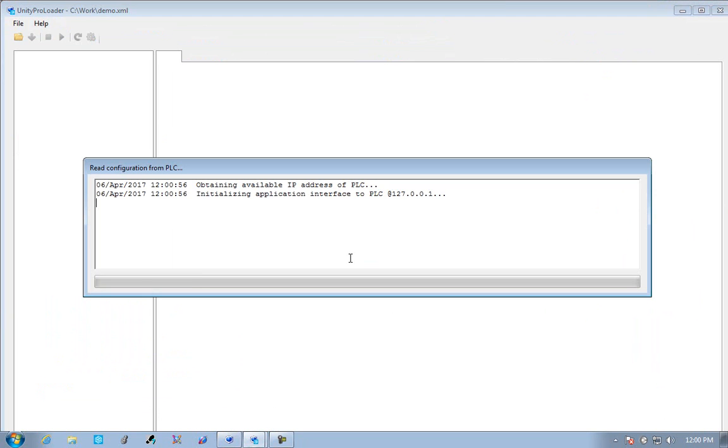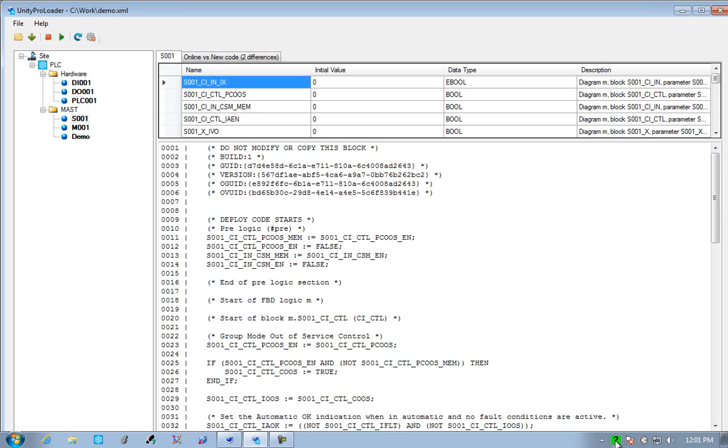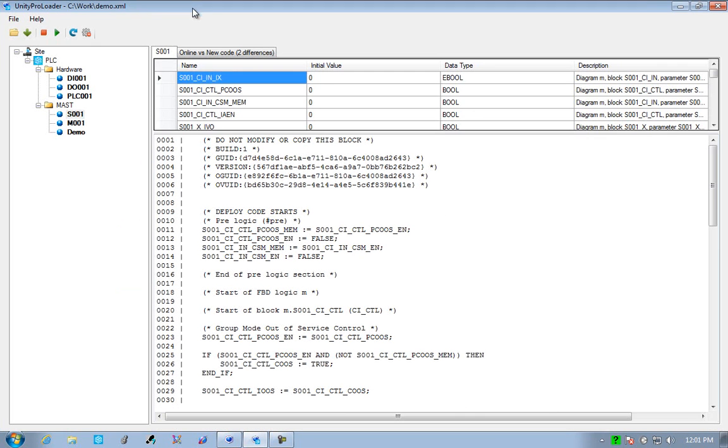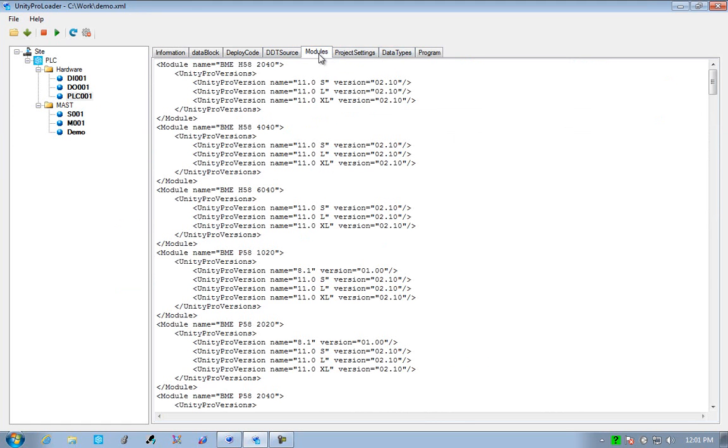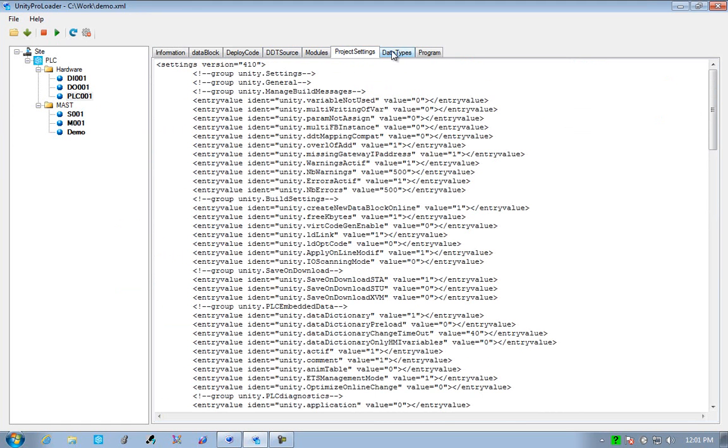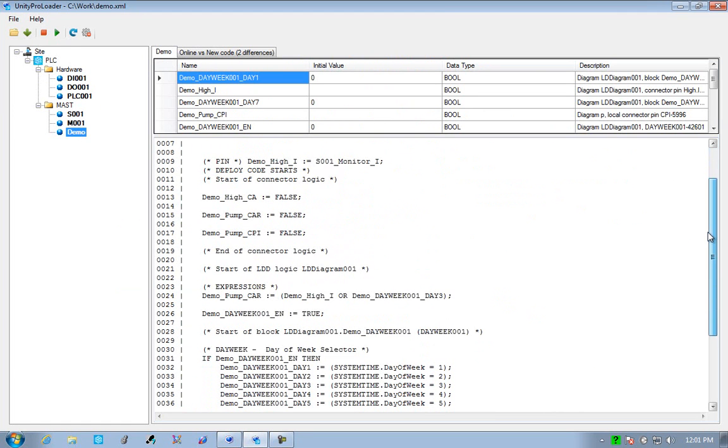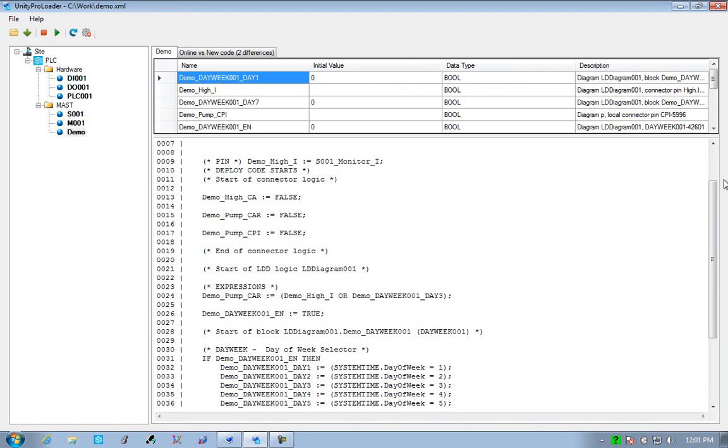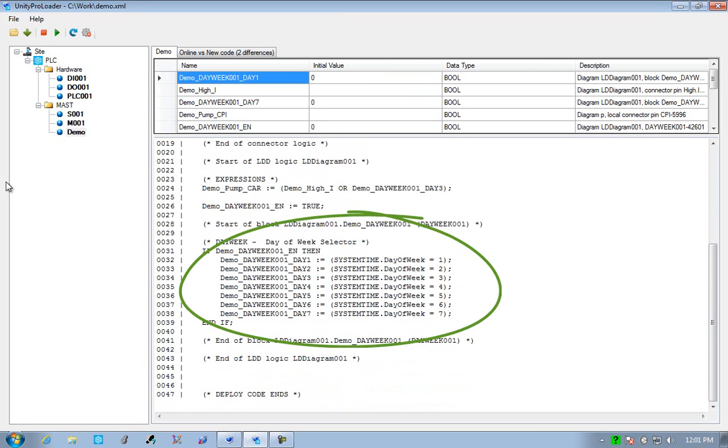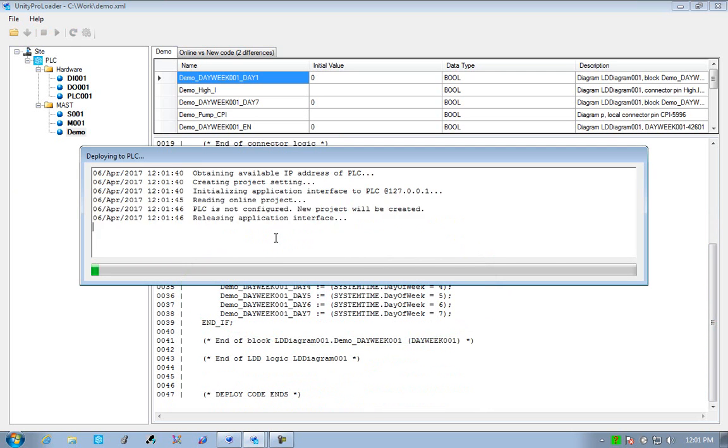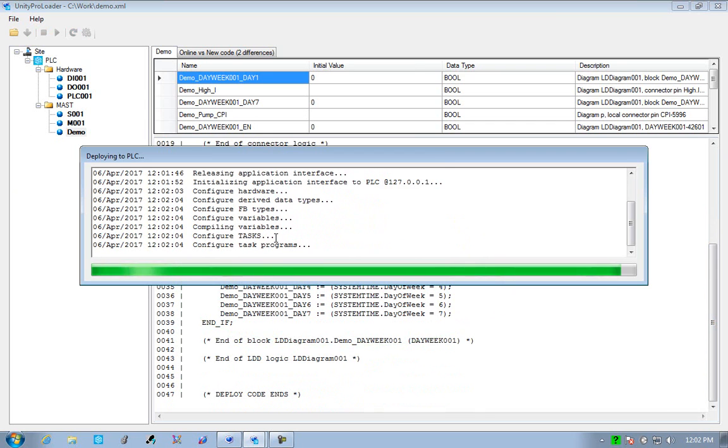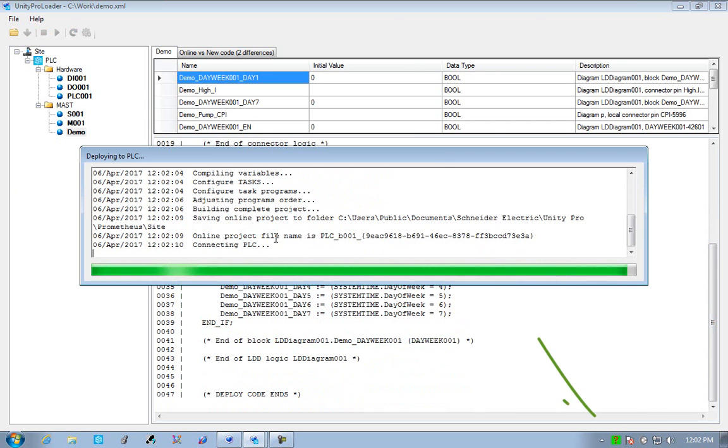Now we run a loader, and the loader is an application specific to the vendor's application. It will now talk to Schneider Electric Unity Pro, and we'll see a preview of what's going to be deployed to the system, as well as the ability to see the full hardware configuration and all the components that are going to go to the controller. But we'll also see tampering. We have a tamper window where we can see the delta. Once again, you'll see the same piece of code again, but now it's ready to go into Unity. It was built in Prometheus, and now it's been tokenized and parsed into the final product, and all the memory and necessary framework to support it within the controller is automatically declared for us.